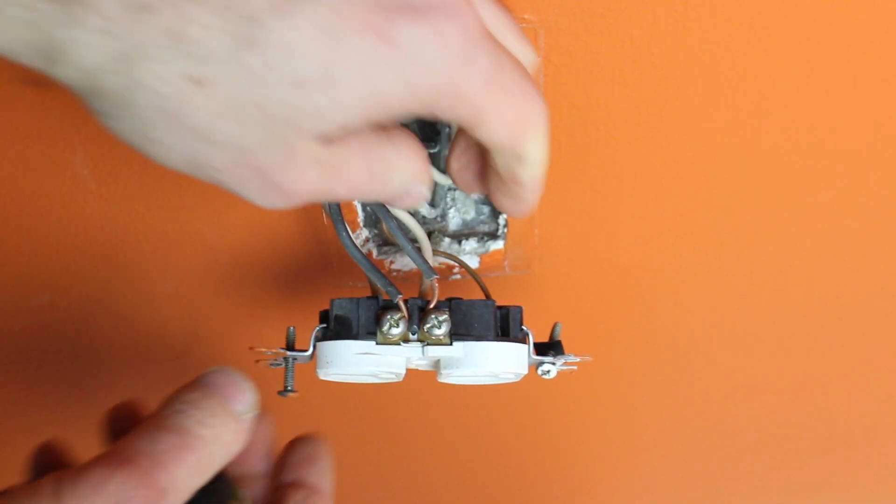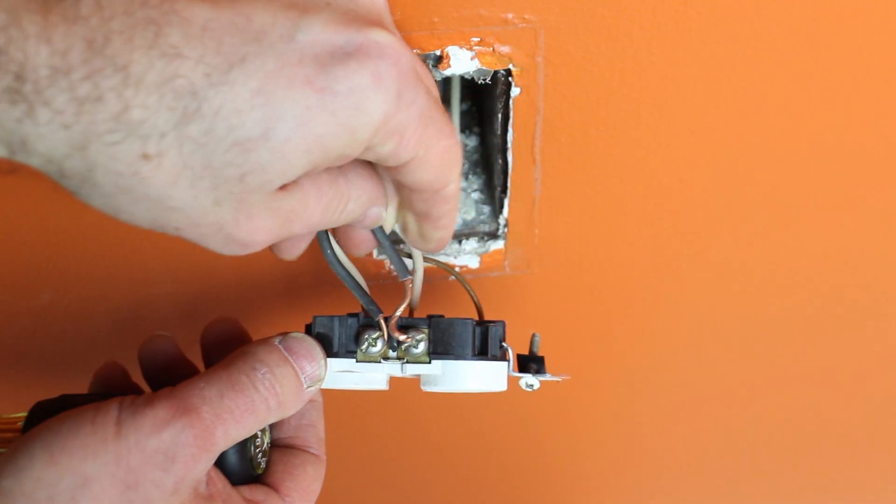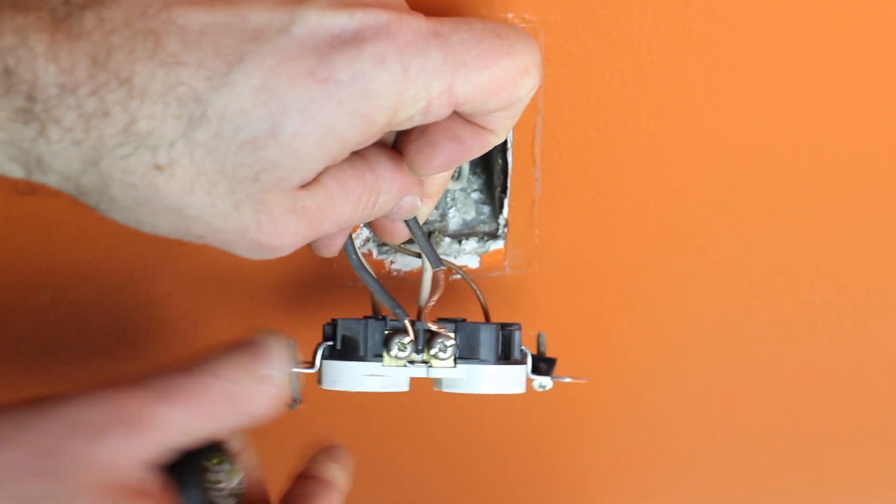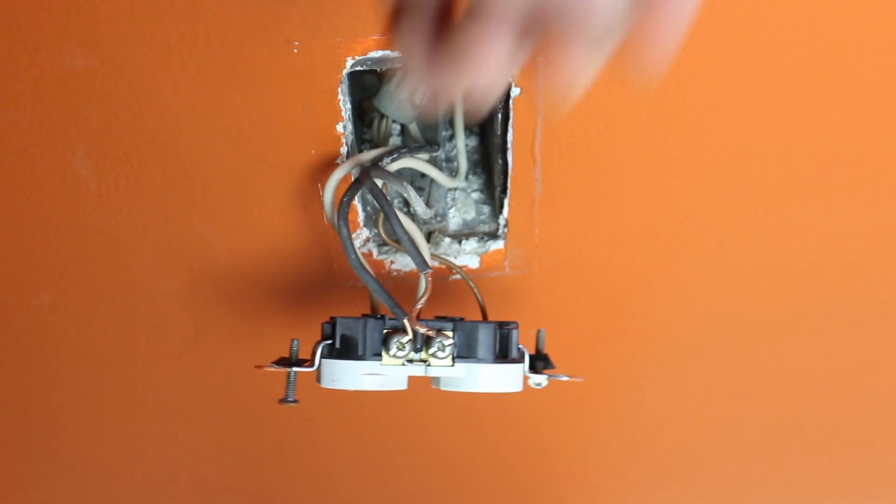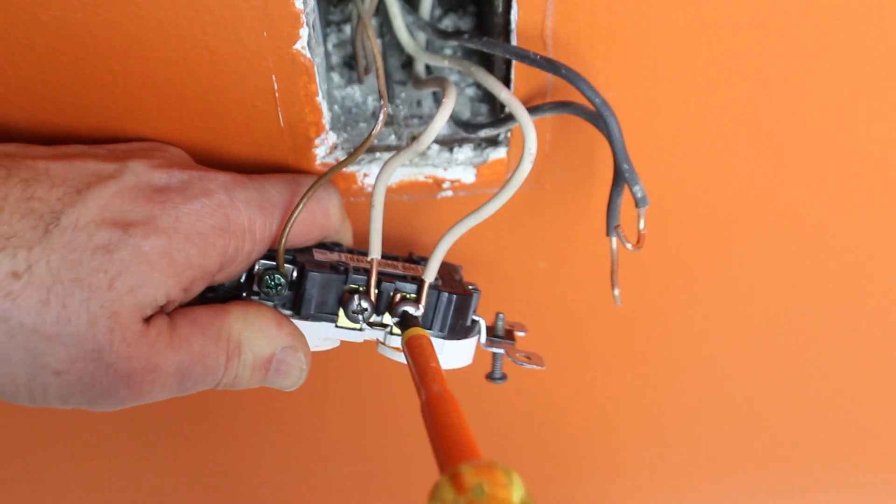So what you need to do first is unwire the hot wires. Here I wanted to show you something. The loop—the wire loop isn't properly looped. And that's dangerous because the hot wire could have came off the terminal screw.